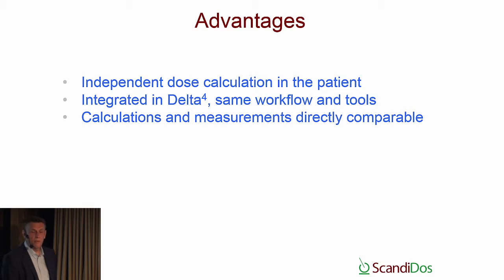So, for example, if you have a discrepancy when you do your pre-treatment verification on the total dose delivery, you could look at subarcs, and then you could compare the subarc dose that you measured with the subarc dose that was calculated. Normally, you don't have this information from the treatment planning system. But that's something you get when you have our treatment planning verification.